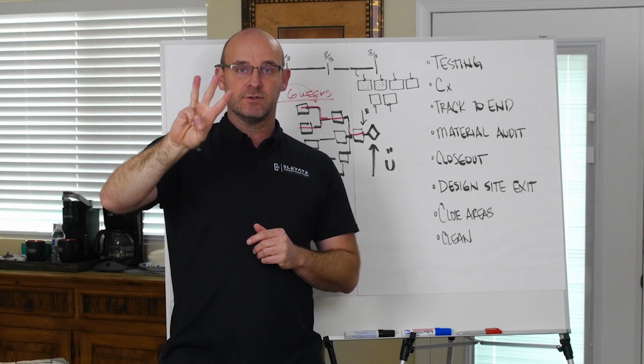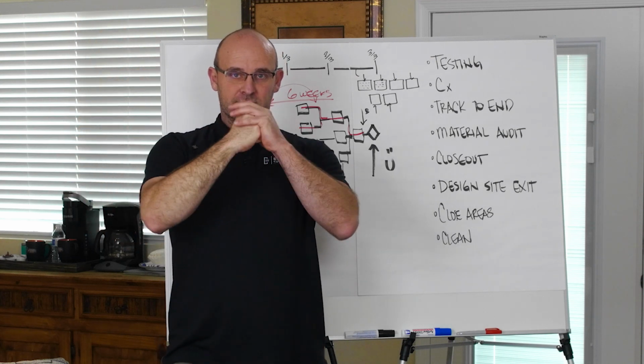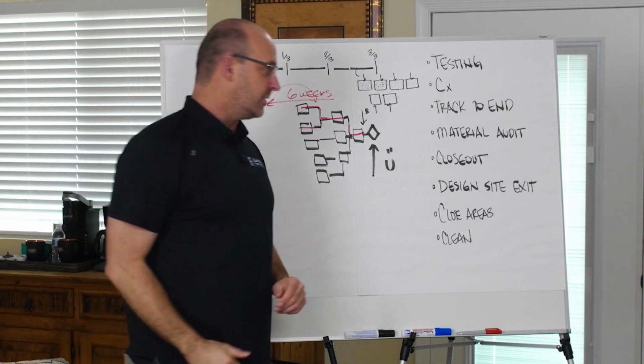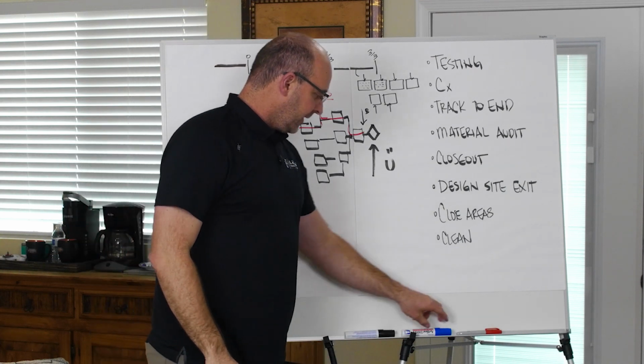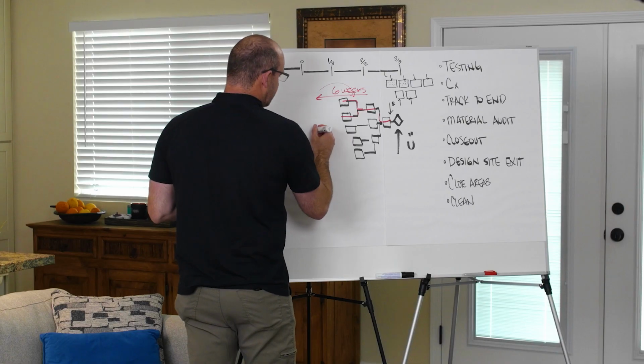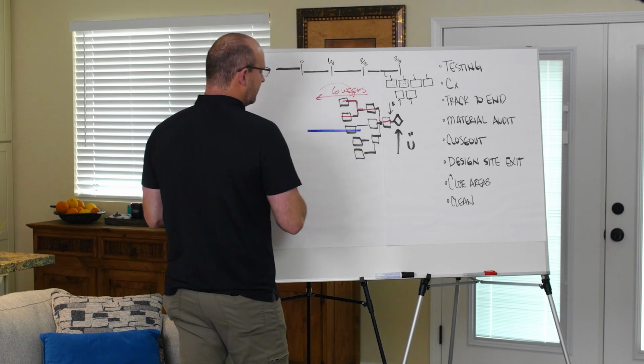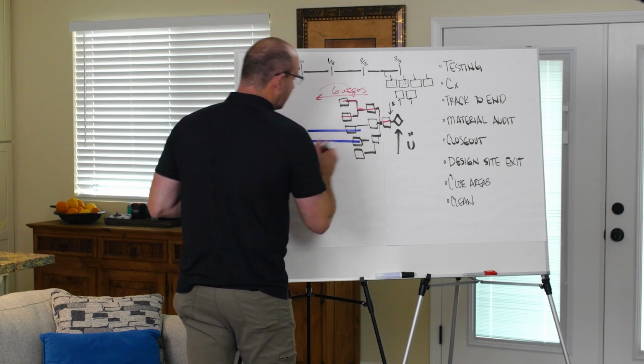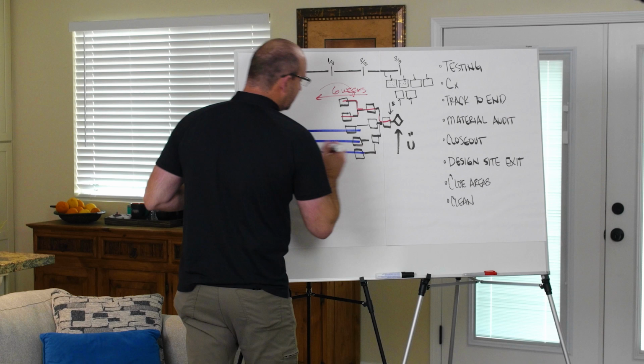And the third thing is you're going to have equipment on every floor, and you're going to have to have your point-to-point done on every floor. All three of those things need to come together to a critical milestone for you to start your commissioning. So you'll have the path up to the air handlers themselves, your electrical and comm coming up, and your commissioning on every floor.